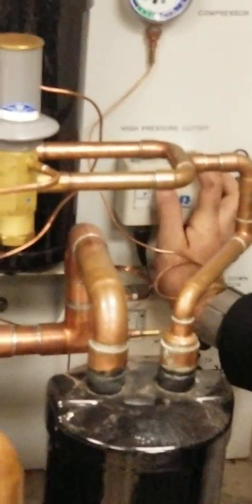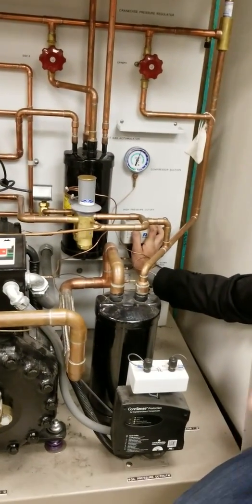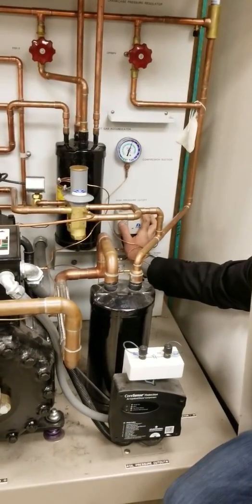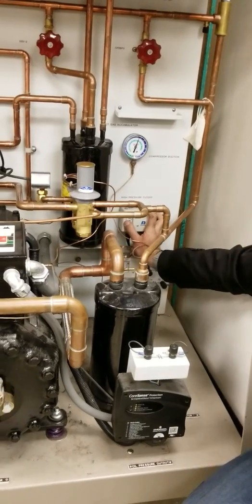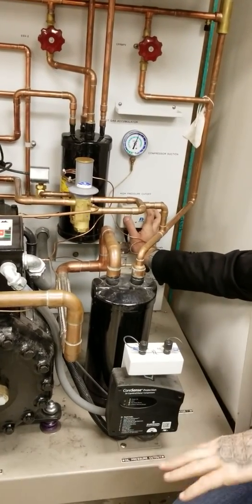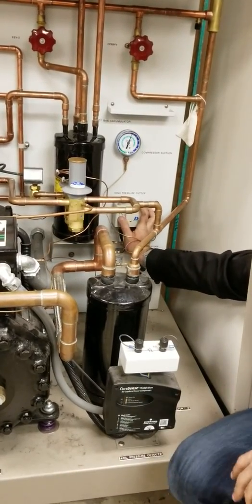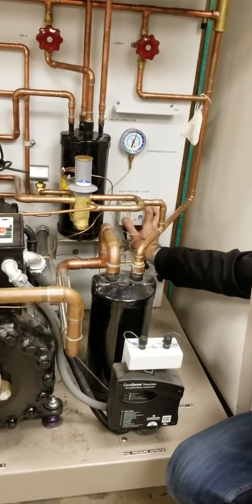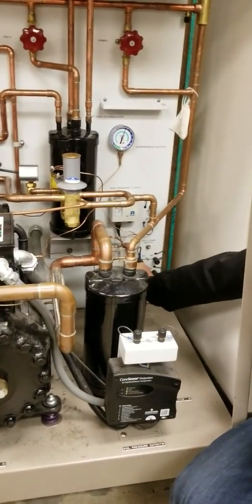So when we get up to 200, boom, triggered. It's not going to come back on until we're down to 160. The high side pressure resets down to 160. The unit will then close the contact and allow the energy to flow again. This one is the same thing, but for low pressure.